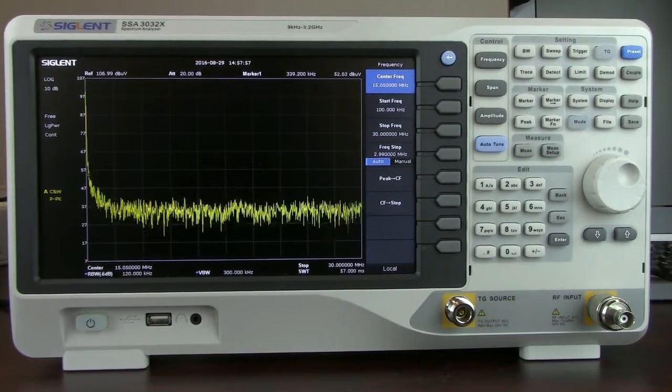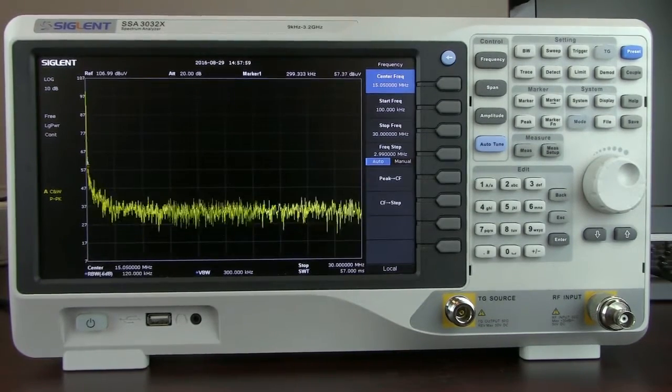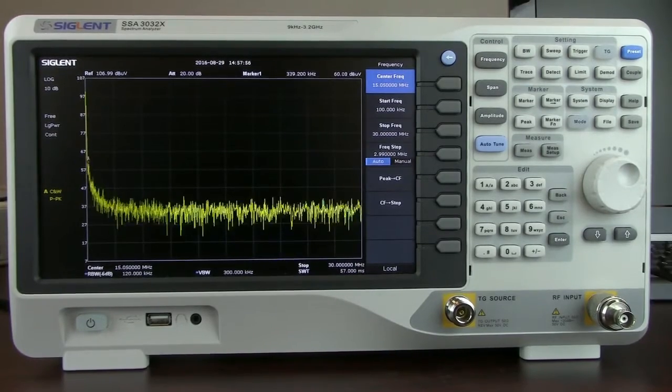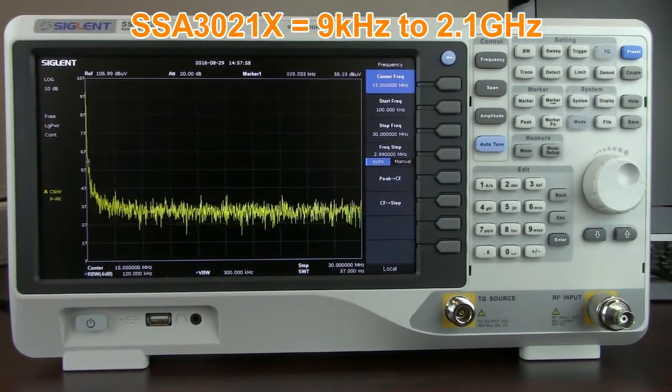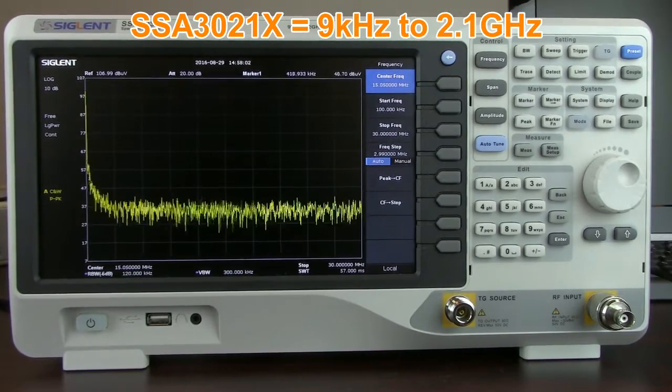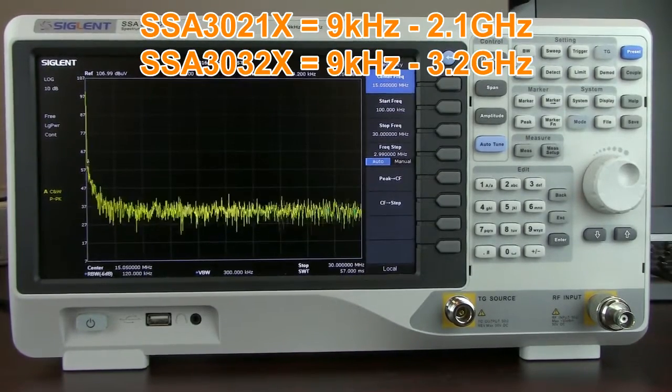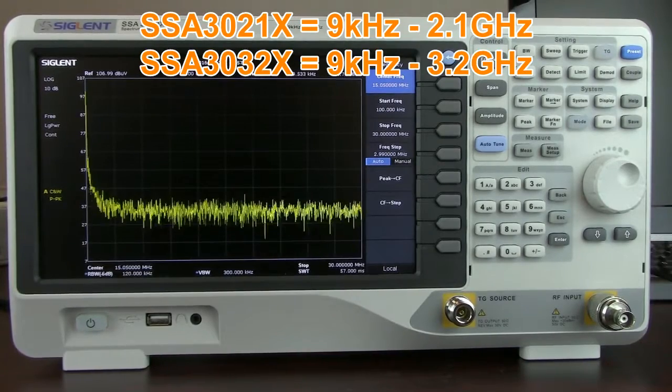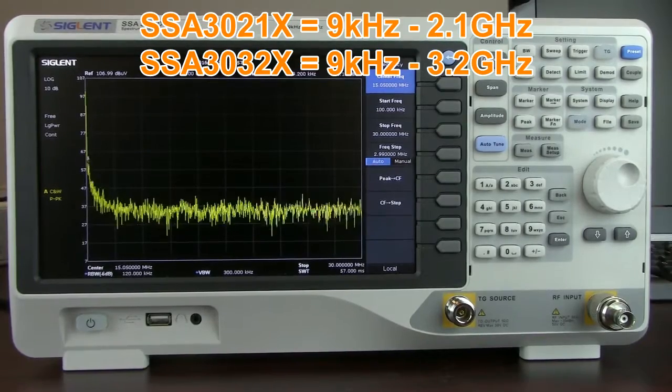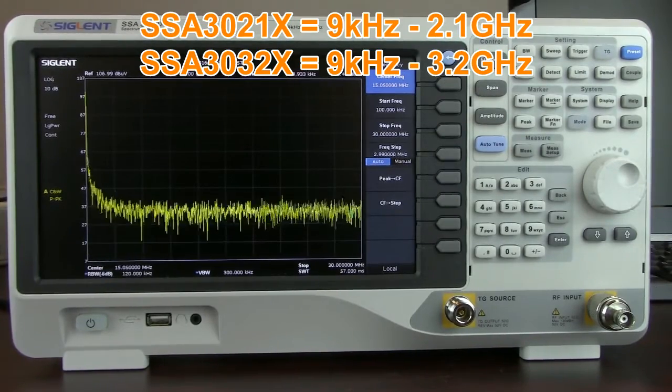In this video we're going to highlight some of the reasons why the SSA 3000X has become so popular. There are currently two models available. The SSA 3021X operates from 9kHz to 2.1GHz and the SSA 3032X operates from 9kHz to 3.2GHz. Both are based on a swept super heterodyne design that has historically provided great performance without a high price tag.